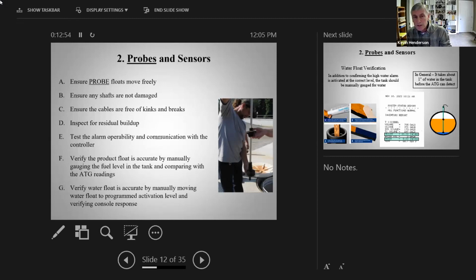Test the alarm, operability, and communication with controller. And again, that's debatable what that really means. If you're doing point 2 testing, the alarm that you're talking about is a failed point 2 test. Well, how do you simulate that? You start pulling the probe. Well, you can. So I don't really know what they're getting at there relative to doing point 2 testing, but we can argue about it, we can talk about it, but the main thing we're trying to do is verify that the floats are actually measuring the fluid levels in the tank correctly.